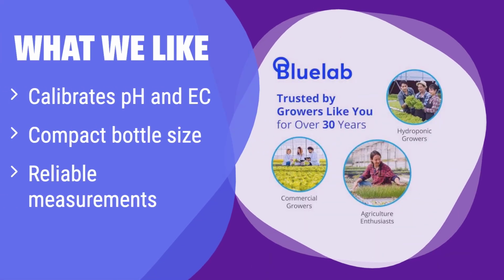What we like: this set provides essential pH and EC calibration solutions in a convenient 250 ml size. It's ideal for those who perform routine maintenance and require dependable results for their hydroponic systems or water quality testing. If you need accurate calibration for both pH and EC meters and prefer a smaller, manageable bottle size for frequent use, this set is a practical option.